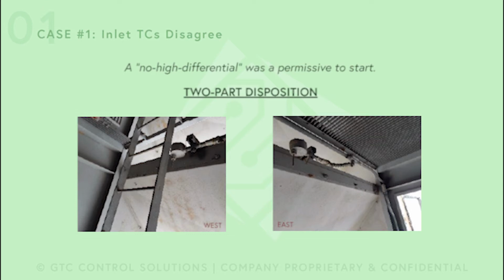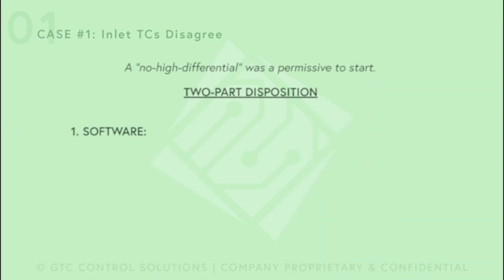So how can we solve this high differential? We looked at it and said, well, you are checking the difference between the thermocouples, and if two have a high difference between the highest and the lowest, the differential is too high, and you have this problem. So let's consider the typical ambient temperatures that you'll find at this location and set those as limits and say, if my thermocouple is reading between these limits, my thermocouple is okay. If my thermocouple is reading beyond these limits, that thermocouple is not okay and I will not consider it.